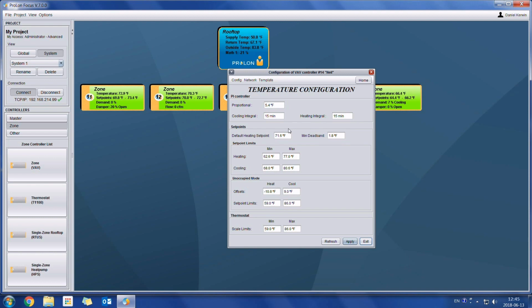So I'm not going to go through every single box in this menu, but what I do want to show is the set point limits, so we can lock the set points in within certain limits. We have unoccupied mode as well, so this is for nighttime setback for energy savings.